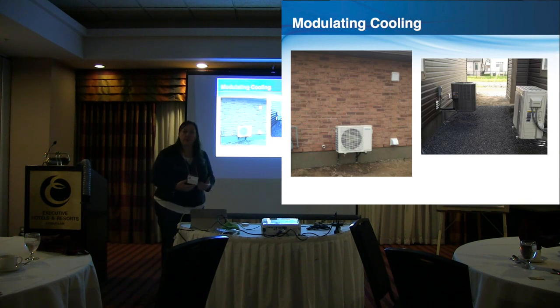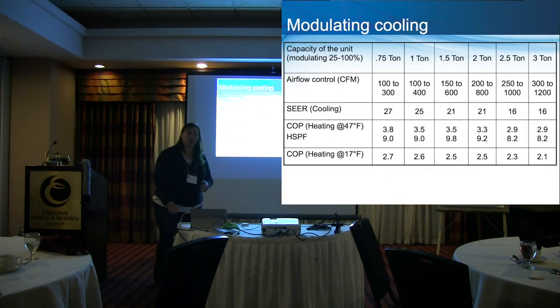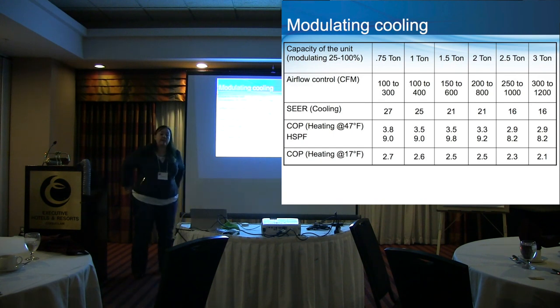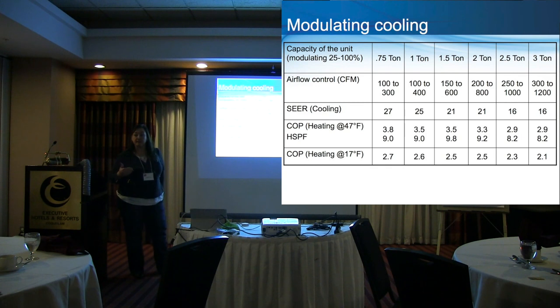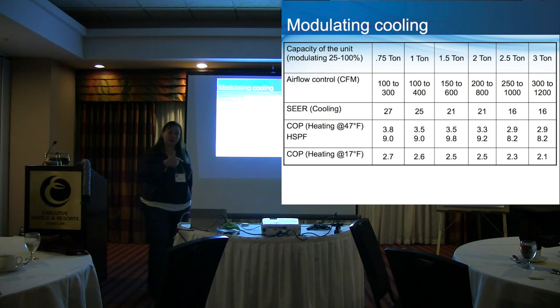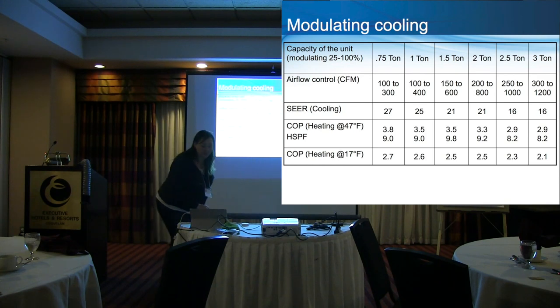And we're getting that modulating equipment again, so able to run cooling at low CFM, longer cycles. Interestingly enough, Doug at that point was putting regular air conditioners in, and he was spending about $500 per house putting a dehumidifier in his houses as well. So when he's transitioned over to the air source heat pump, and I'll show you that we've interlocked everything in at 200 CFM, now in the summer, because that air is crossing the A coil slowly, he's getting dehumidification at the same time. So he's been able to take those dehumidifiers out of his house. You guys don't have the same humidity issues as he does in southwestern Ontario.